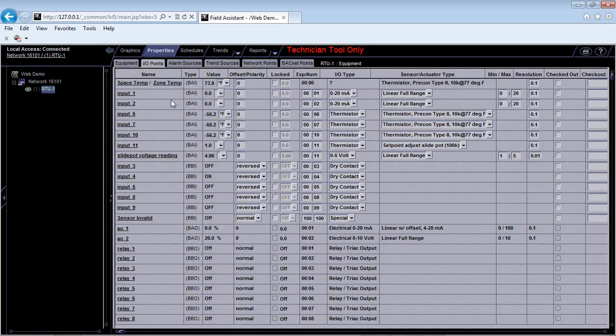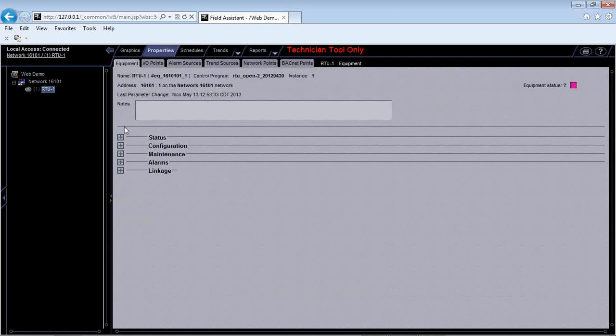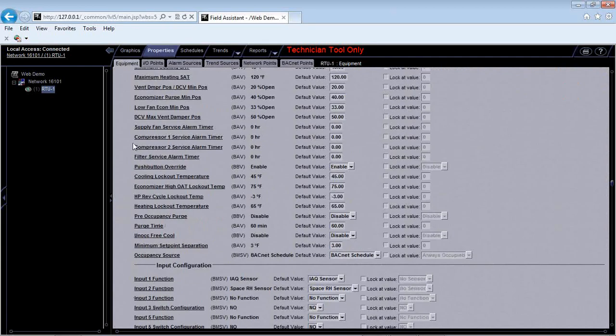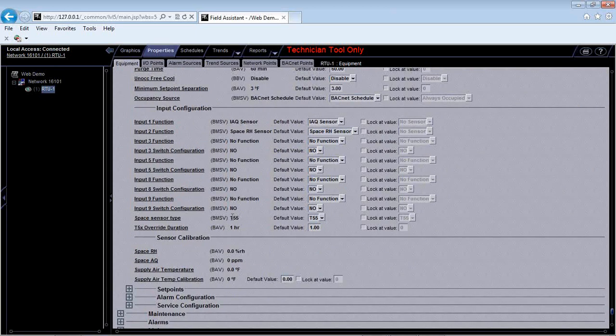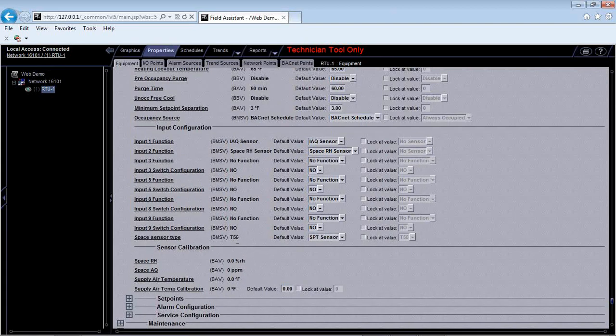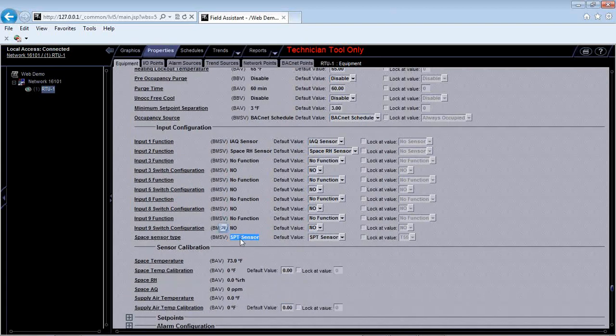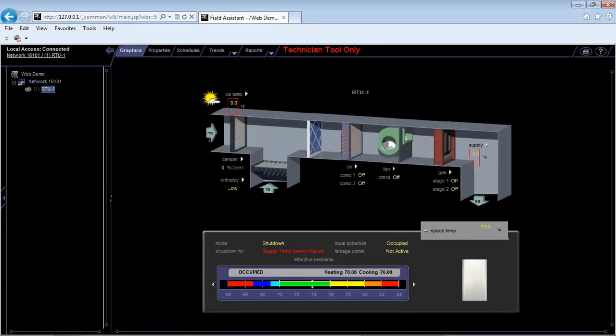And you can actually see that I'm reading a space temperature value here, but I'm in space temperature shutdown alarm. What that means is I probably have the wrong space temperature sensor configured. So if I go to equipment configuration, unit configuration, I'm set up for a T55 sensor. I actually have an SPT sensor in there. So if I click SPT sensor, hit OK, wait for this to take here. Now I go back to my graphic, and I'm actually getting a space temperature reading now of 73.9, okay?